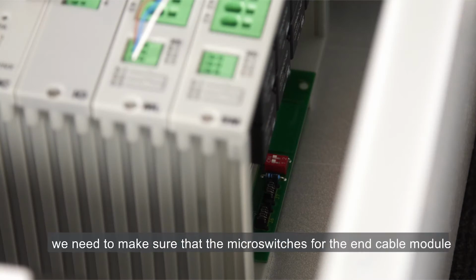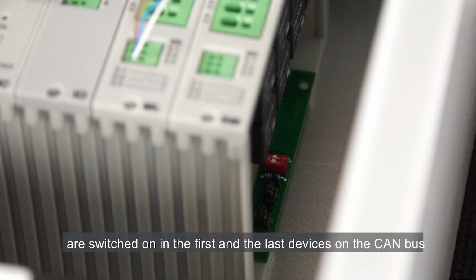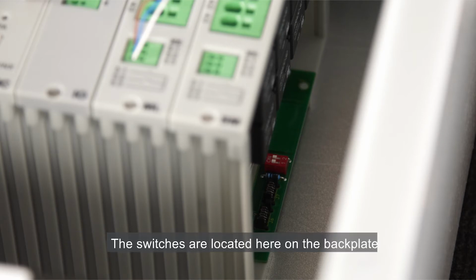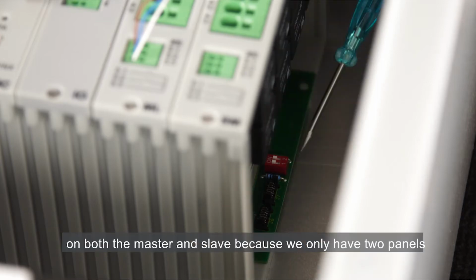After connecting the CAN bus cable, we need to make sure that micro switches for the end cable module are switched on in the first and the last devices on the CAN bus. The switches are located here on the back plate. I've turned them on both the master and slave because we only have two panels.